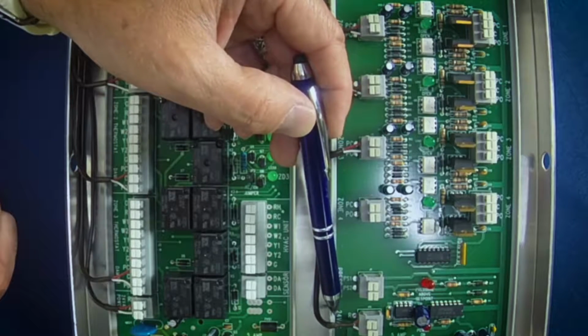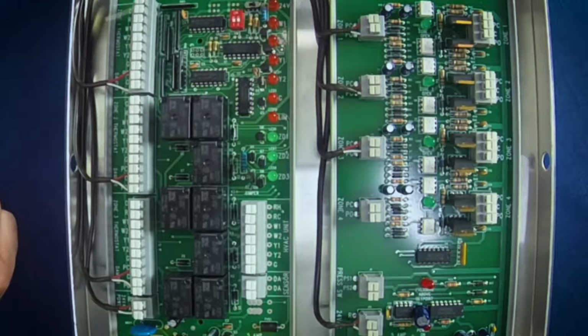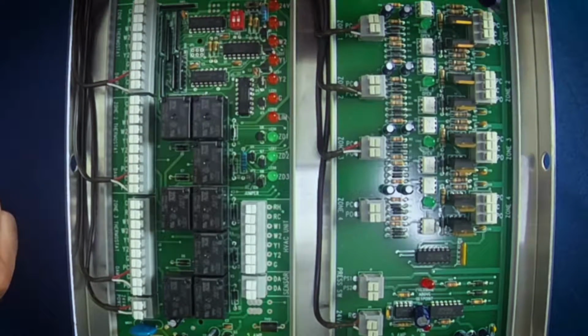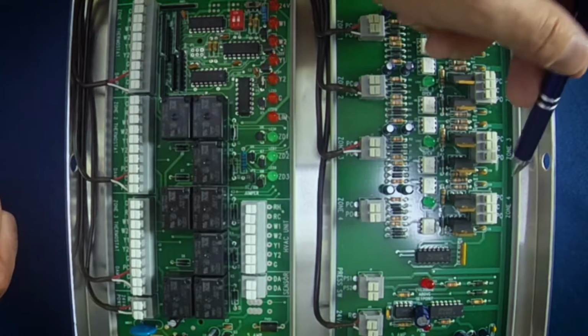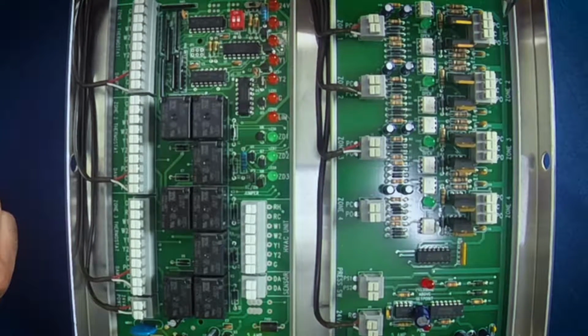ESP panel. Now, where you're going to actually run your 3 wires is when you actually go ahead and you've got zone 1, 2, 3, and 4 on the ESP panel. So this is where you're going to actually have your power closed, your common, and your power open. These are where your dampers are actually going to wire in.